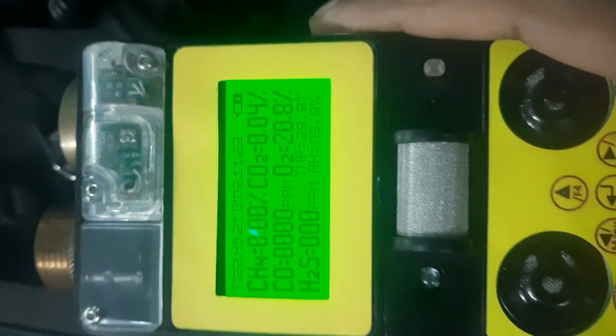Okay, now I am connecting this fan for measurement of air velocity. Now it came to air velocity mode. When we move this fan, you can see the air velocity. It measures air velocity from 0 to some values, and when you remove this fan again, it comes back to main mode.